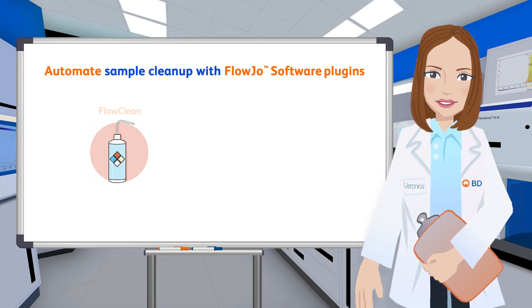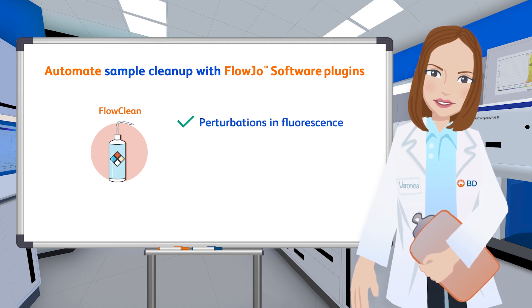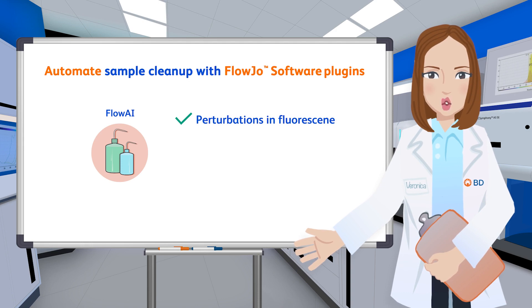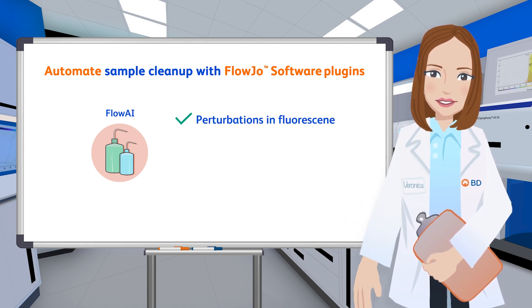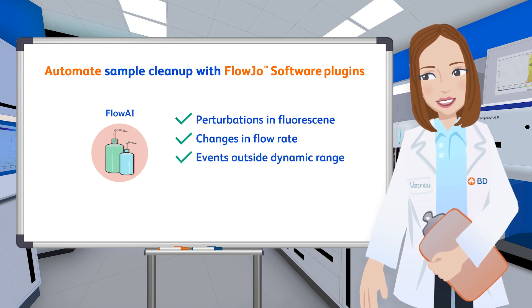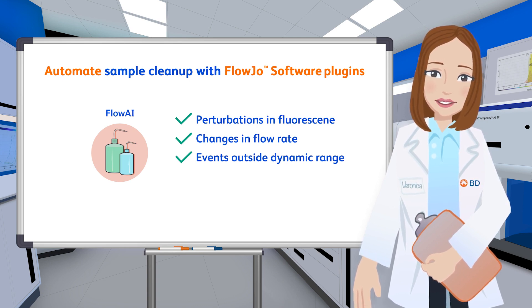The FlowClean plugin splits data into equally sized time bins and identifies periods where subpopulations are abnormally represented relative to the rest of the dataset. The FlowAI plugin detects fluorescent perturbations across parameters, like FlowClean, but also checks for changes in flow rate and fluorescent events outside the dynamic range of the instrument. The FlowAI plugin also creates a report to describe the source of excluded events.